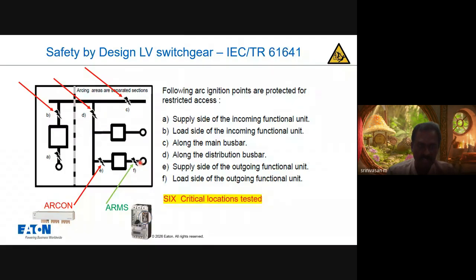But if an internal arc happens on the incoming side of the outgoing breaker, or in the main busbar, dropper busbar or the incomer ACB cubicle, it will be difficult for the FM team to carry out the maintenance or replacement. Suppose the internal arc happens in the main busbar chamber. We are sure that the FM team may not have the busbars and supports as spare items. So if such a big internal arc happens in the main busbar or dropper busbar, they definitely need to call the particular panel builder or OEM manufacturer. They need to come to the site and replace all the busbars and supports. Depending upon the severity, it may take a few days, sometimes even a week or 10 days, to replace the complete busbar system.